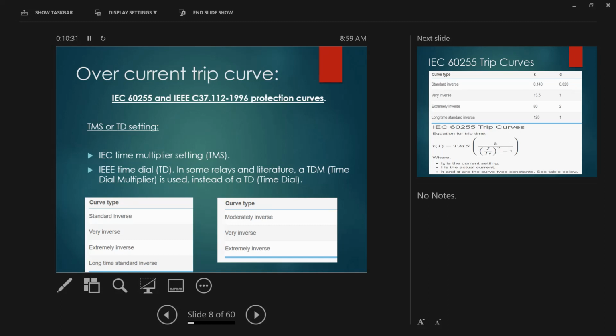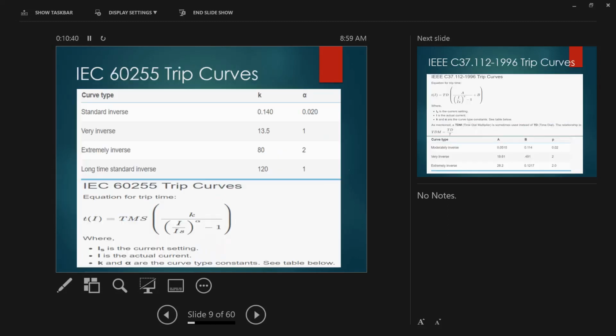The IEC one is standard inverse; there are 4, up to long inverse. In IEEE, you have 3. So that's where the curve comes from. In the IEC, mostly it's the TMS that you get on the relay settings. The duration of time is based on this and also on your overload. You can get the constants here. As a formula, K will be there, your alpha will be there, and your TMS from the relay. You can then check the expected time when you inject the current, depending on how many percent.